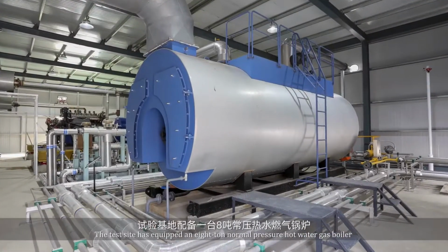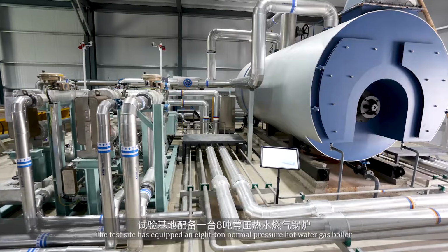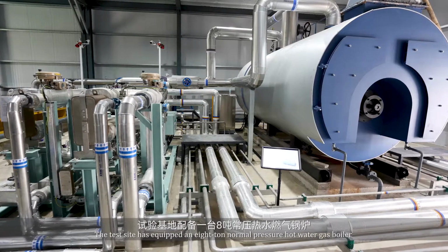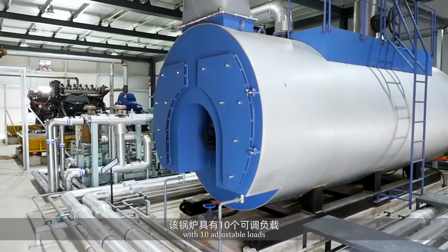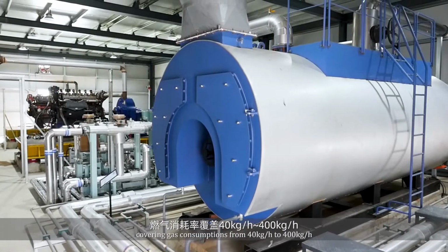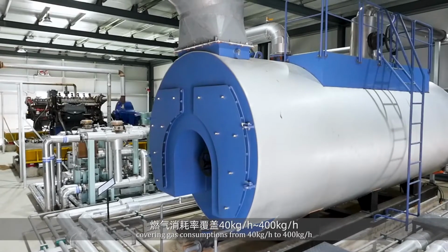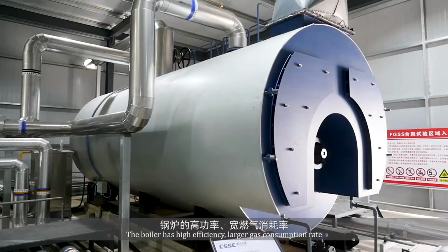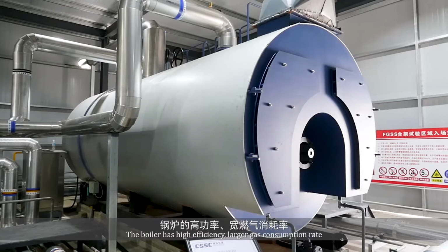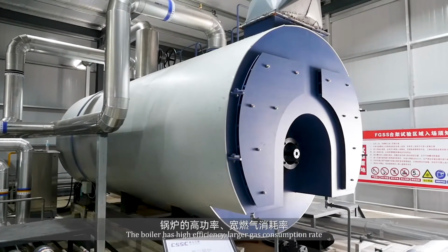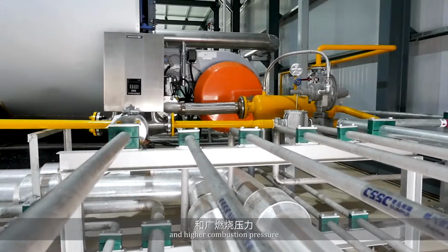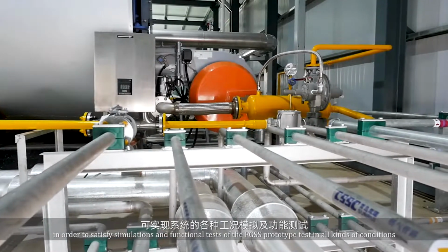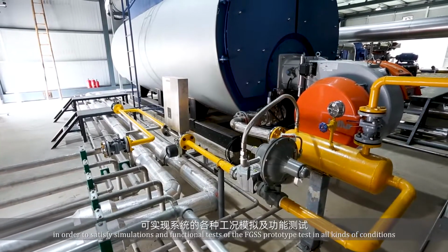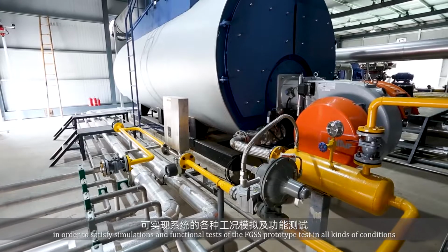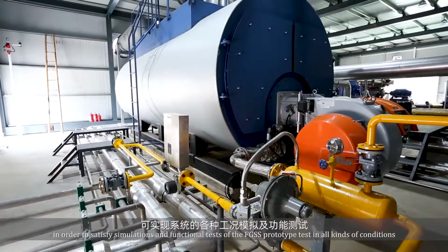The test site is equipped with an 8-ton normal pressure hot water gas boiler with 10 adjustable loads, covering gas consumption from 40 kilograms per hour to 400 kilograms per hour. The boiler has high efficiency, larger gas consumption rate, and higher combustion pressure in order to satisfy simulations and functional tests of the FGSS prototype test in all kinds of conditions.